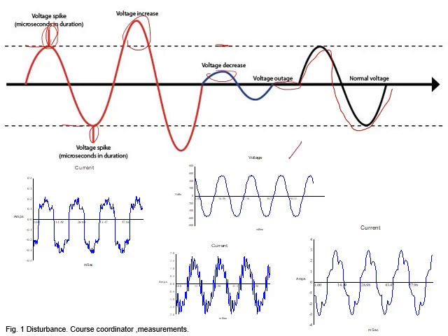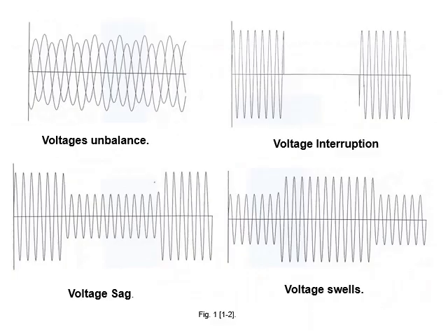Now these figures are waveforms that I measured myself in Sohar industrial area maybe 20 years back, using a power harmonic analyzer. As you can see here, it's not pure sinusoidal. You see the voltage, you see the current. It's affected by many processes through the electrical circuits because of the load, but at the end, it affects other loads connected to the same supply.